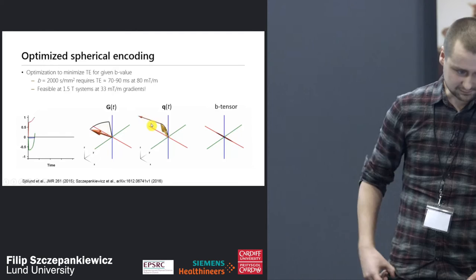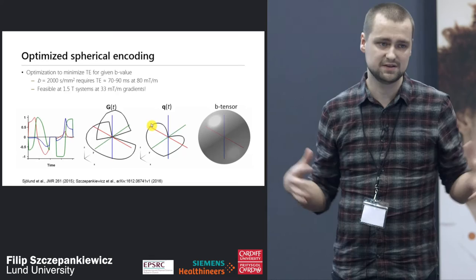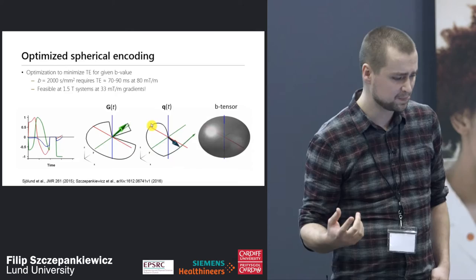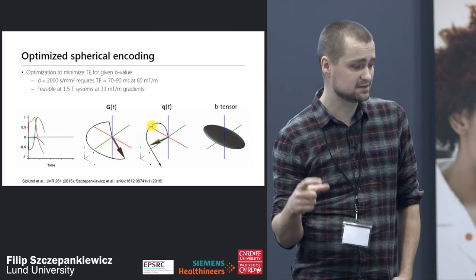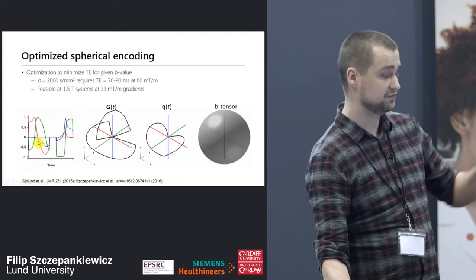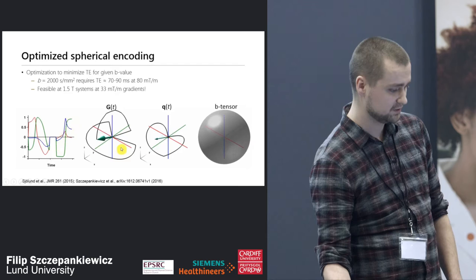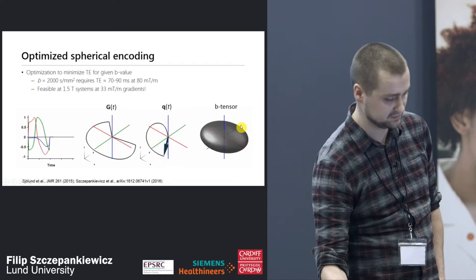In practice, this is one of the optimized waveforms we use, demanding as little time as possible to minimize echo time. For a B value of 2000, we require about 70 to 90 milliseconds echo time at 80 mT/m. We've done these experiments at the Connectome scanner and at Prismas, but also at 1.5 tesla systems with gradients as weak as 33 mT/m. The waveform fits into a spin echo — excitation before, refocusing in the middle with gradients off, then continuing encoding afterwards. We have this gradient trajectory, the Q trajectory, and we can see how the B tensor grows during time — this one is specifically isotropic.